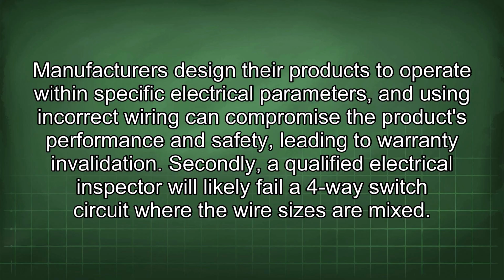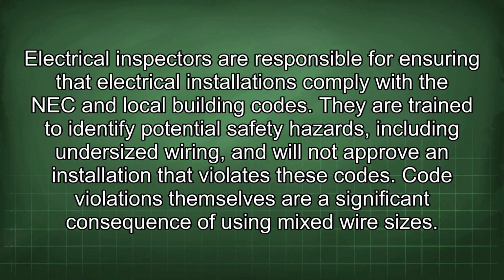Secondly, a qualified electrical inspector will likely fail a four-way switch circuit where the wire sizes are mixed. Electrical inspectors are responsible for ensuring that electrical installations comply with the NEC and local building codes. They are trained to identify potential safety hazards, including undersized wiring, and will not approve an installation that violates these codes. Code violations themselves are a significant consequence of using mixed wire sizes.